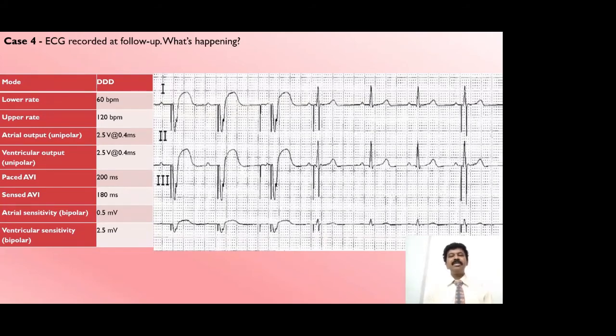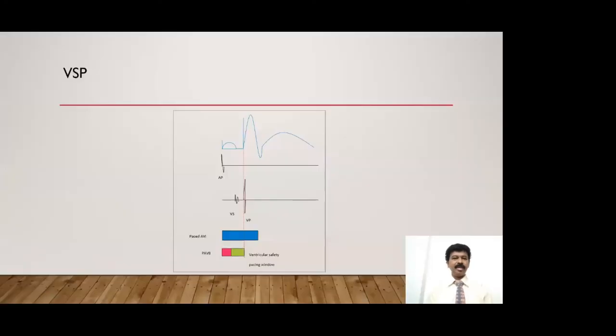This is the classical ventricular safety pacing feature of the dual chamber modes. So these are the important findings here. Here is maybe A sense, V sense. Again, ventricular safety pacing here. Remember, ventricular safety pacing happens only after atrial pacing, not during atrial sensing mode. This is to ensure that the ventricle is 100% paced, especially in ventricular pacing dependence. So once it paces the atrium, as soon as it senses a little in the ventricular channel, it ensures that the ventricle is being paced.